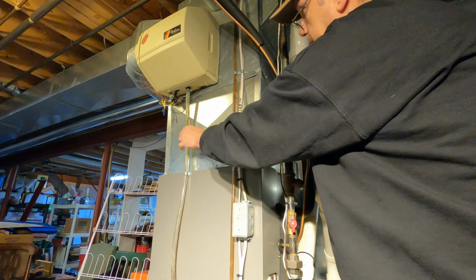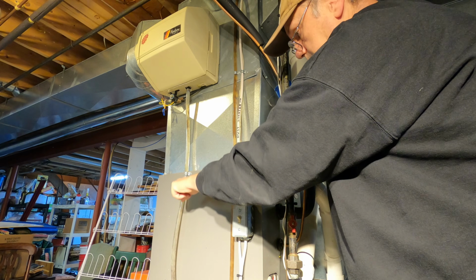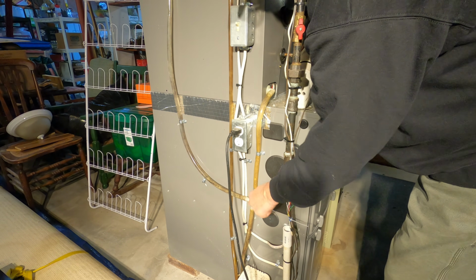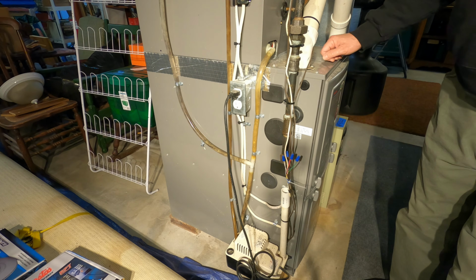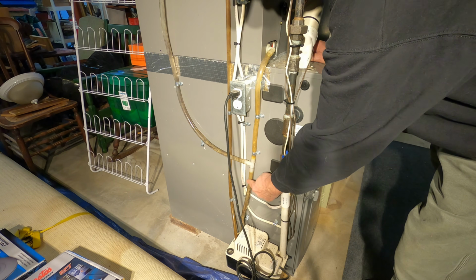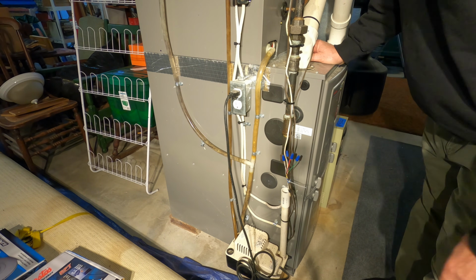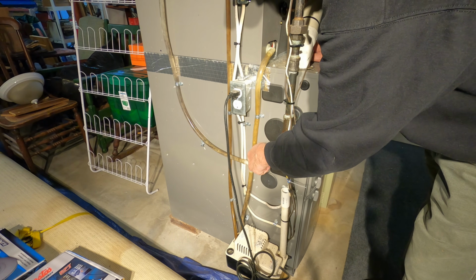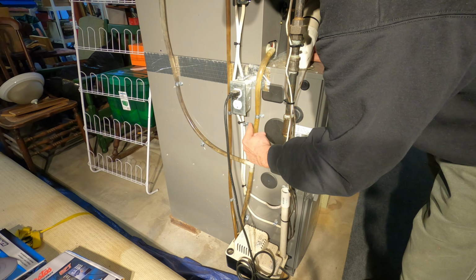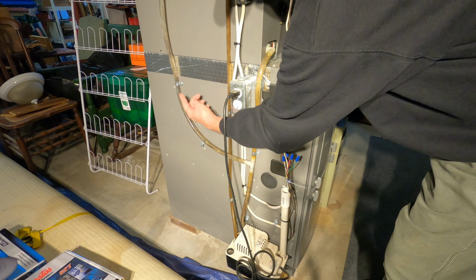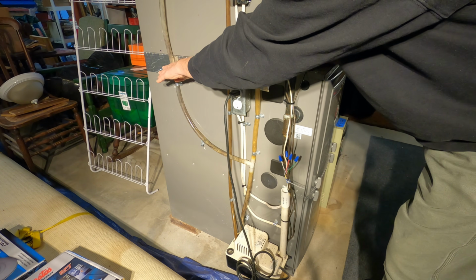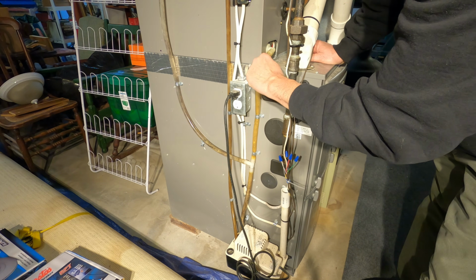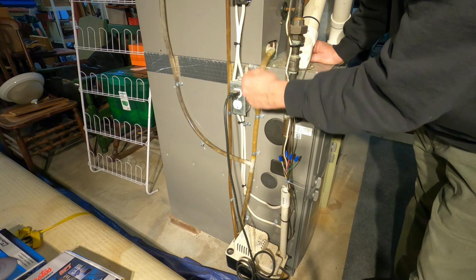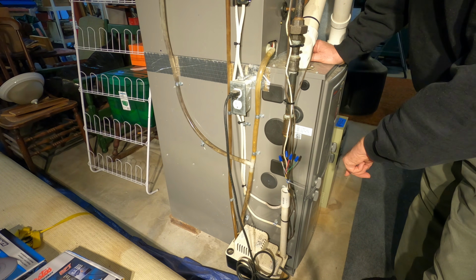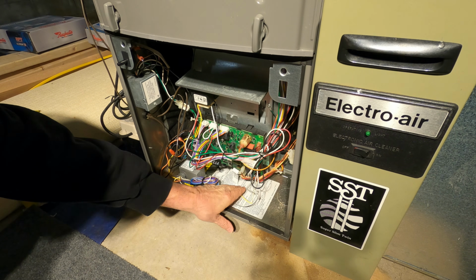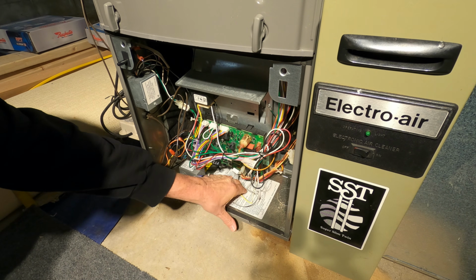In addition to that, there's a drain tube coming out of the humidifier that runs down and tees into this drain tube and down into the condensate pump. So the problem I had here was that just below this tee, the line got plugged. It was just plugged with a bunch of schmutz that built up in there, started up here and built up, and the water from both here and here stopped flowing. They both backed up. This line was actually full all the way up to the level of this drain. But inside the evaporator housing, since the water had no place to go, it started dripping down inside the furnace. The relay, or really any electrical items, shouldn't be mounted on the bottom of the cabinet here.